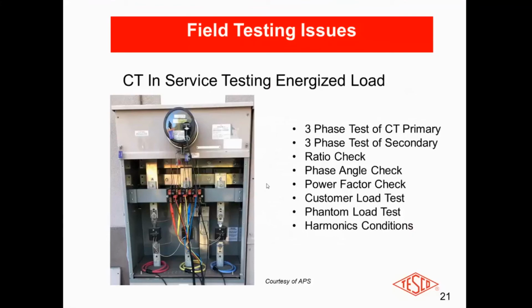Let's look at some of the field testing issues in an energized load using standard probes. This has been done for many, many years. This is a typical service panel with the meter, as you can see. We have a test switch in the center there in that bar, which we're connected to with our duckbills, which go into the red, yellow, blue, which is ABC. And you can see the voltage connections.